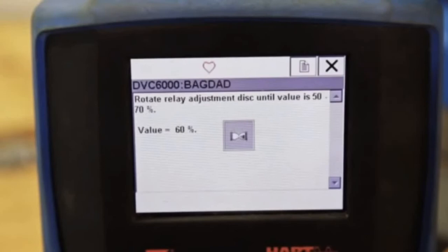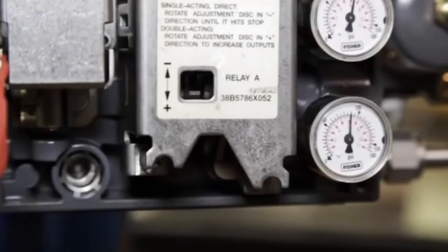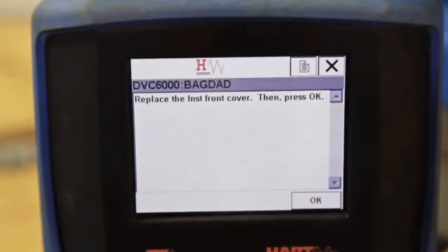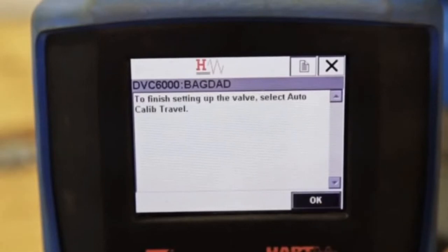Slowly adjust the relay disc until the value reads between 50 and 70%. Use a flathead screwdriver to move the relay adjustment disc up or down until the desired value is met. After adjusting, wait several seconds for the positioner to settle. Small adjustments to the disc can make big changes to the value. Replace the cover and select OK.